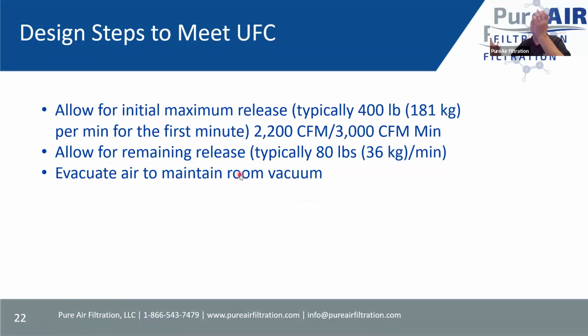Basically, what this is, we need to allow for the initial maximum release. Again, what we're saying is that you need, at a minimum, 2,200 CFM to 3,000 CFM to maintain a vacuum to be able to scrub, or pull in, or overcome this 400 pounds after the first minute, then the 80 pounds after the initial release.